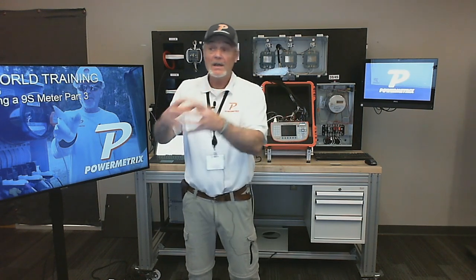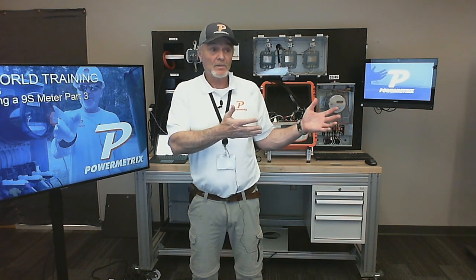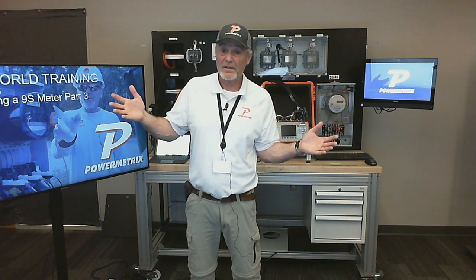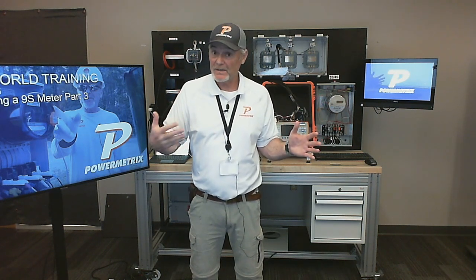You worry about when you change the customers at a site and don't change the CTs - you and I fight that all the time, don't we? Used to be 800 to 5s, and the customer was enough there that 800 to 5s were warranted. Now another customer comes in without nearly the load the previous one did, but we didn't change those 800 to 5 CTs. So now we're way on that back end, the light end, trying to test them. It already puts us in a curveball because they didn't change those CTs out.